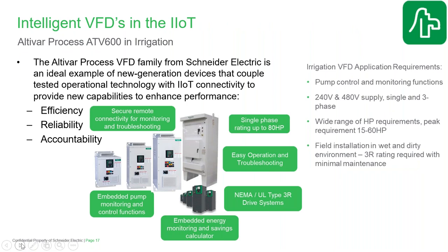When it comes to pumping, and irrigation pumping in particular, if we're looking at how we integrate intelligent VFDs in there, the types of VFDs you need have to address the basic requirements for irrigation. So you need to have pump control capability and pump monitoring capability. You need to be able to operate on the power supplies commonly available, typically 240, 480 volt supplies, very often three phase, but in many areas, single phase is the only one that's available. So you need to be able to operate off a single phase supply. It also needs to take into account the environment for installation: it needs to be suitable for outdoor installation and minimal maintenance under those conditions.